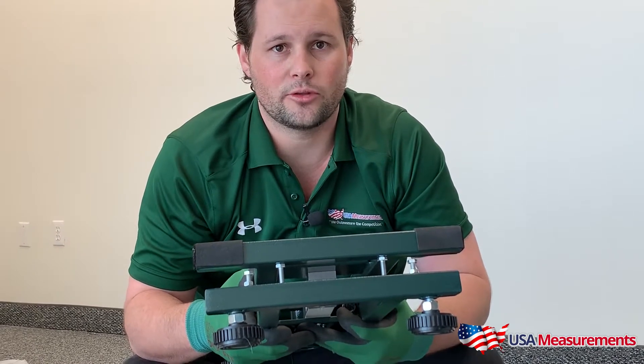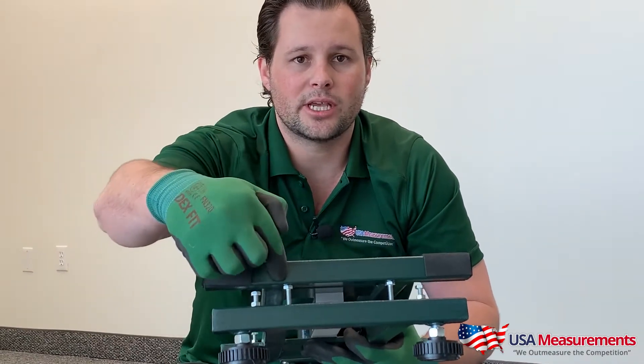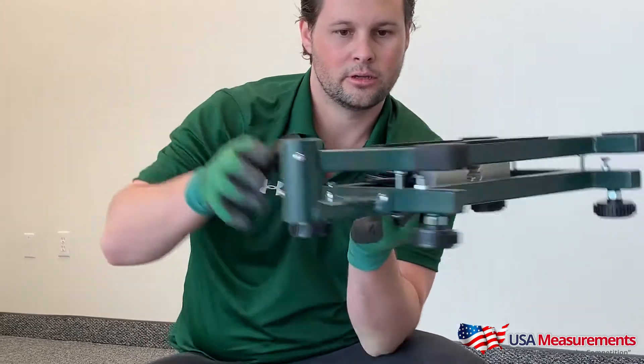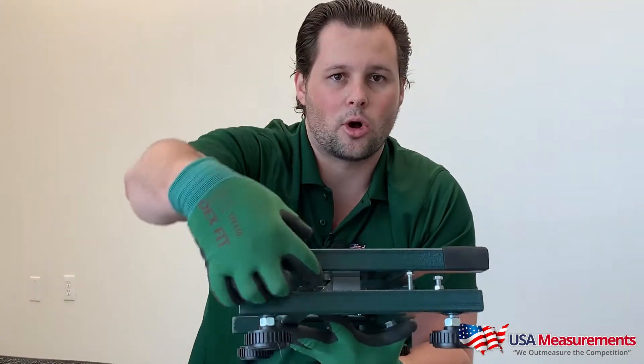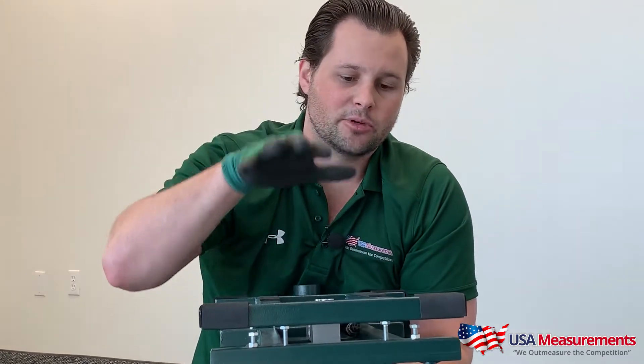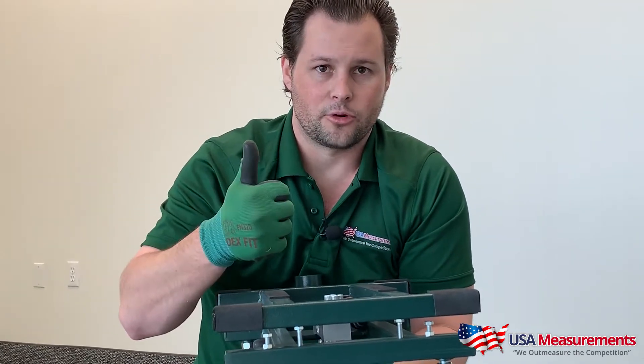So here's one of the most important things: when we ship our scales, we want to make sure that they don't get damaged in shipping. So what we do is we put these safety screws in place on all four of these corners here. When you get the shipment, before you start using it, you need to unscrew them all the way to make sure that you can get a weight here, and this protects it from being overloaded. So make sure that you release these safety screws before you start using it.